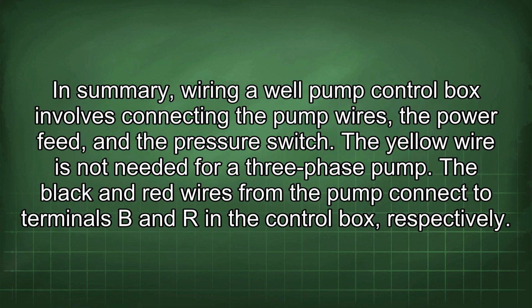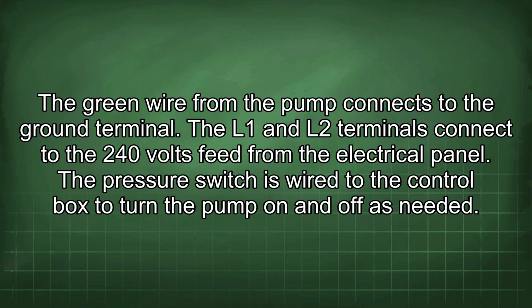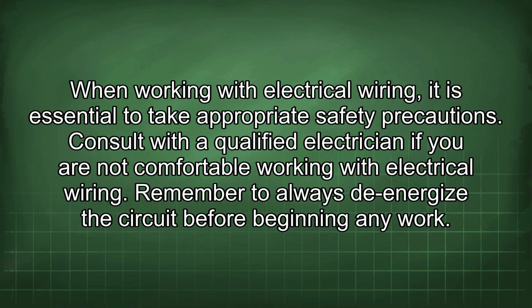In summary, wiring a well pump control box involves connecting the pump wires, the power feed, and the pressure switch. The yellow wire is not needed for a three-phase pump. The black and red wires from the pump connect to terminals B and R in the control box, respectively. The green wire from the pump connects to the ground terminal. The L1 and L2 terminals connect to the 240 volts feed from the electrical panel. The pressure switch is wired to the control box to turn the pump on and off as needed. When working with electrical wiring, it is essential to take appropriate safety precautions.